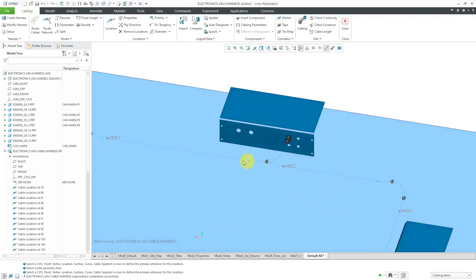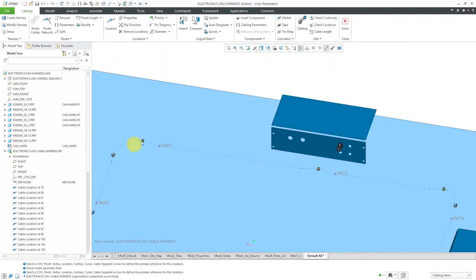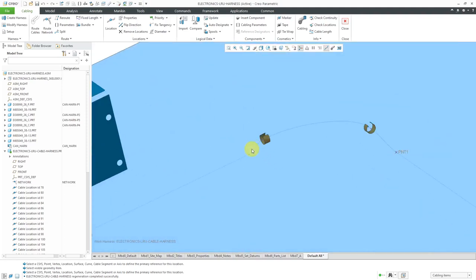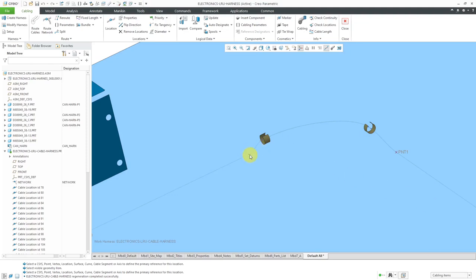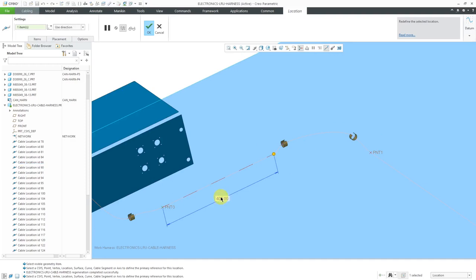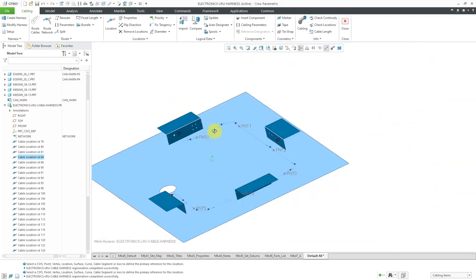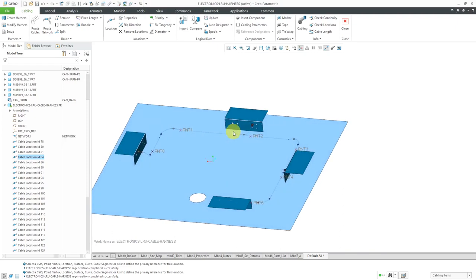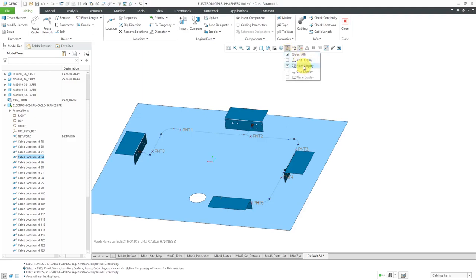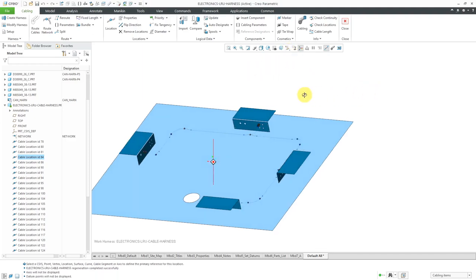I think one of my location points might be a little too close to one of the clips over here, and this might cause problems with the minimum bend radius. So let me select it and choose edit definition — change this to 375, just a little further away, and hit the check mark. Be aware that there's a balance for location points: you don't want too many, you don't want too few. One of the big problems with having too many is satisfying the minimum bend radius. Now let's turn off the axis display and the point display — we have our network.